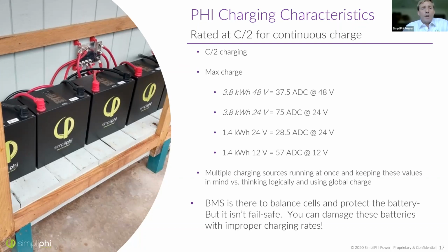You have to be careful not to have a second charging source, like an inverter with AC charging built in, running at the same time. These two charging sources could both be going, so you want to either choose an inverter with the charge controller built in, or have your MPPT able to communicate with your inverter. If not, adjust your settings carefully.